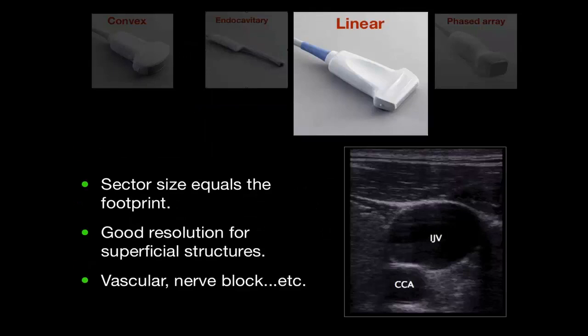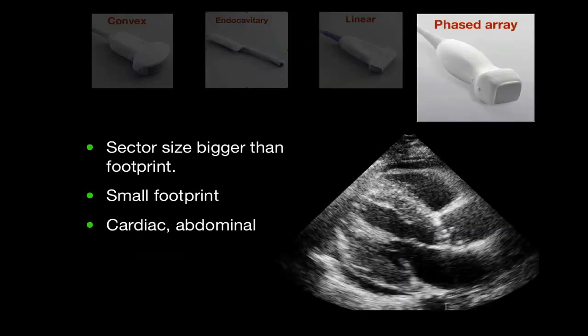The linear probe has a sector size equal exactly to the footprint, is a high-resolution probe, and is used most of the time for vascular imaging or ultrasound-guided procedures. The phased array has a sector size bigger than its small footprint, making it very suitable for small acoustic windows, like viewing the heart in the intercostal space.